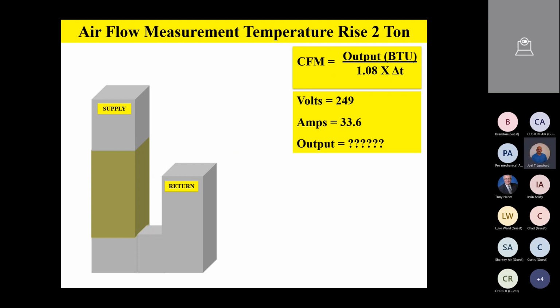And so I've got my calculator out as well, my little handheld calculator. So in this first example here, this is a 2-ton unit. I get the thing running. I make sure the outdoor unit is off, and I've got 249 volts. That's my actual measured voltage with this thing running. I take my amp probe and I snap on there, and I see that my amperage is 33.6. So if I take 249 on my calculator times the amperage of 33.6 amps, and then multiply that times 3.413, that should give me an output in BTUs of around 28,500 and change.